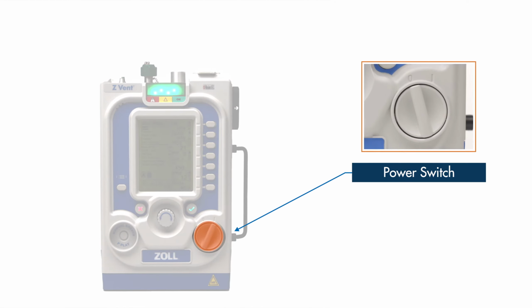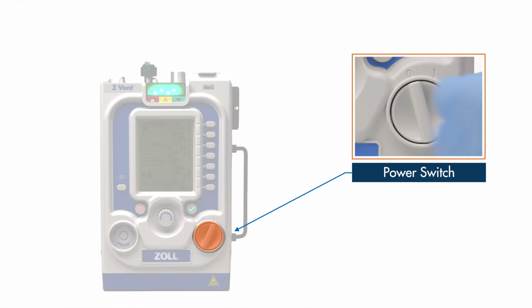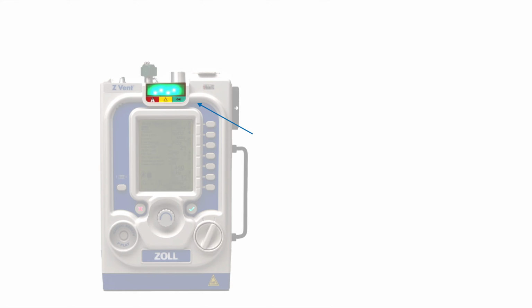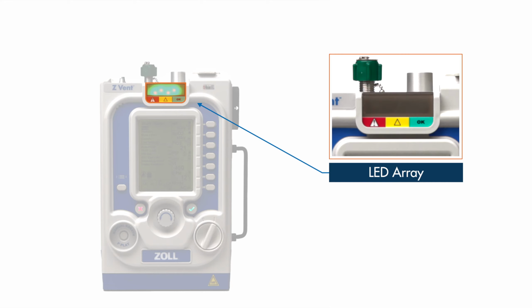In the lower right corner is the power switch. Simply turn the dial clockwise from 0 to 1 to power the device on, and counterclockwise to power down. At the top is the LED array, which indicates the ventilator's operational status. In addition to audible alarms and on-screen prompts, the LEDs will change to yellow or red to alert the care provider of an error. The LEDs will turn green when no alarms or errors are present.